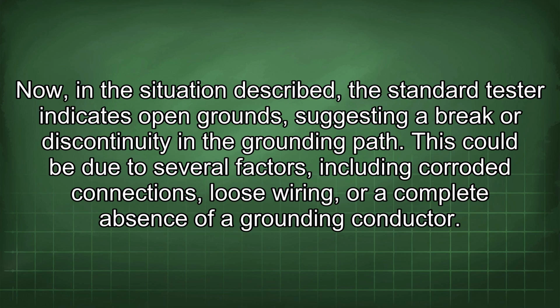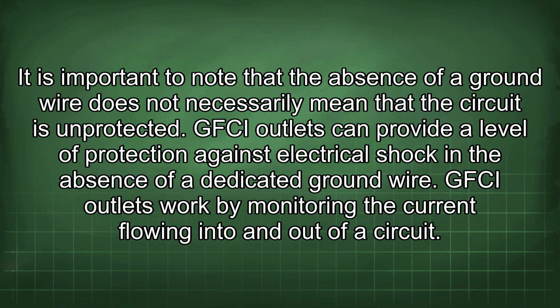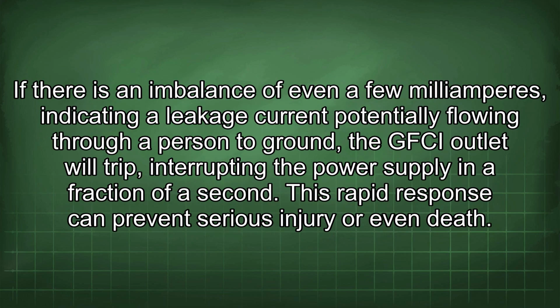This could be due to several factors, including corroded connections, loose wiring, or a complete absence of a grounding conductor. It is important to note that the absence of a ground wire does not necessarily mean that the circuit is unprotected. GFCI outlets can provide a level of protection against electrical shock in the absence of a dedicated ground wire. GFCI outlets work by monitoring the current flowing into and out of a circuit. If there is an imbalance of even a few milliamperes, indicating a leakage current potentially flowing through a person to ground, the GFCI outlet will trip, interrupting the power supply in a fraction of a second. This rapid response can prevent serious injury or even death.